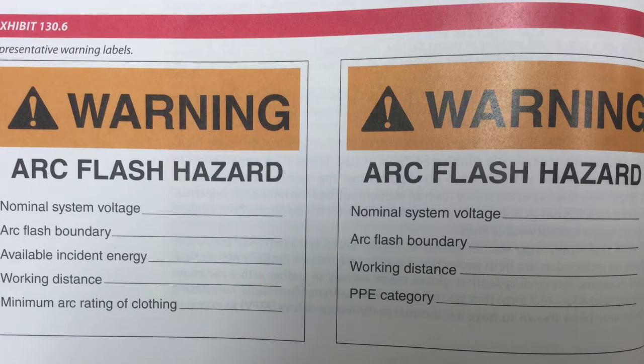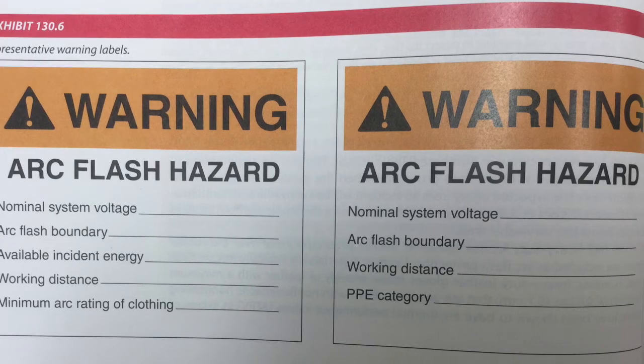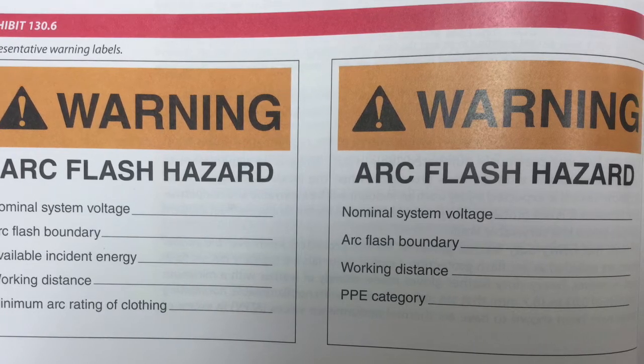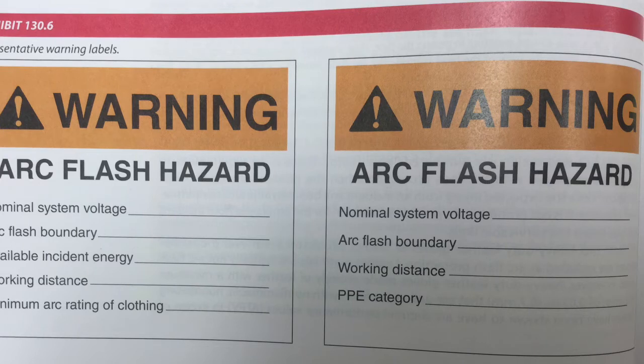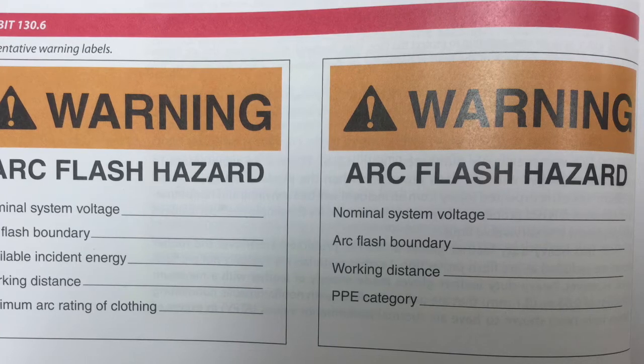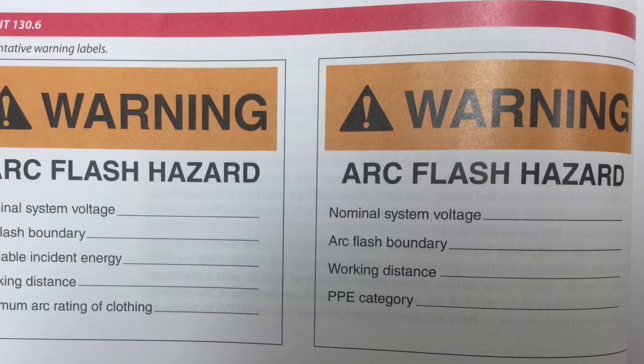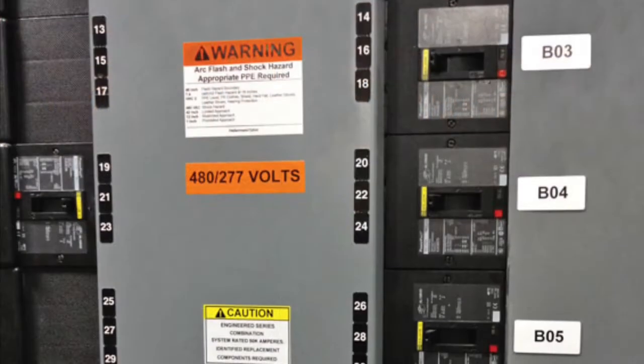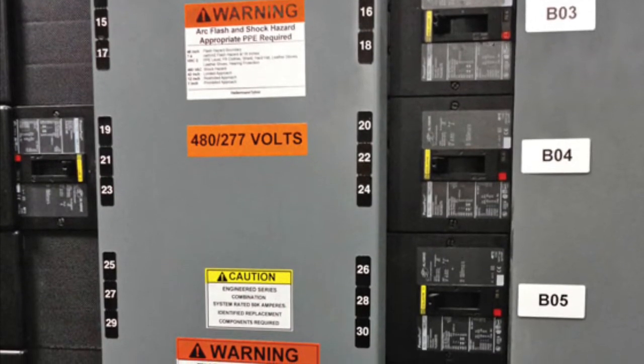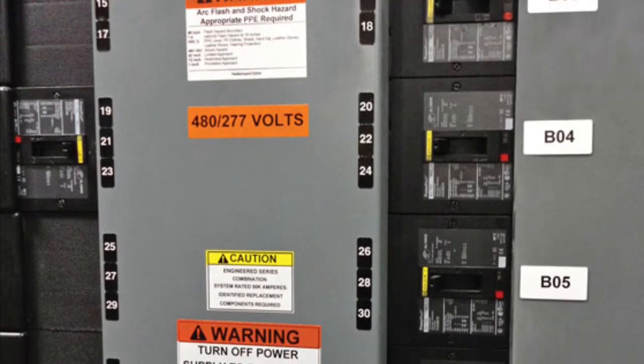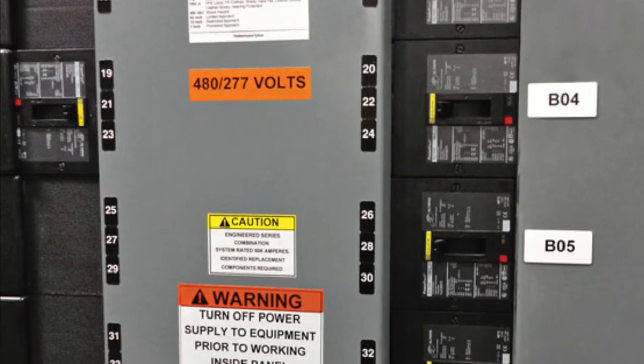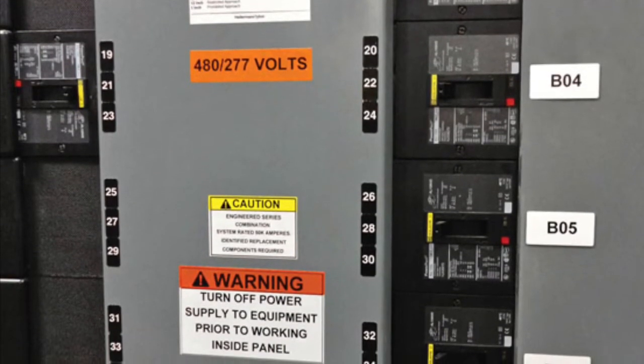Labels should contain nominal system voltage, arc flash boundary, available incident energy, and the corresponding working distance, or the arc flash PPE category for the equipment. An incident energy and a PPE category should not be on the same piece of equipment — only one method of risk assessment may be applied. The method of calculating and the data to support the label shall be documented and reviewed for accuracy at intervals not to exceed 5 years. Where review identifies a change that renders the label inaccurate, the label shall be updated. The owner of the electrical equipment shall be responsible for documentation, installation, and maintenance of the marked label.